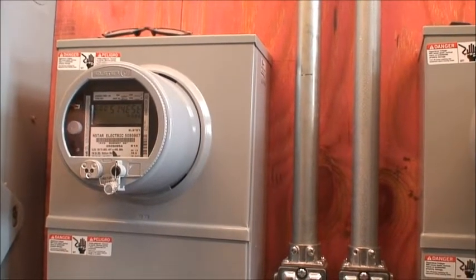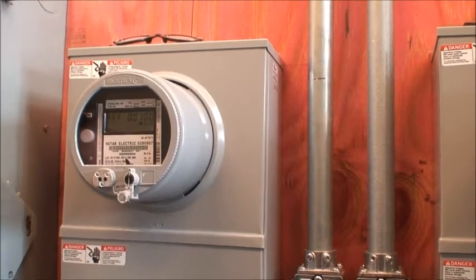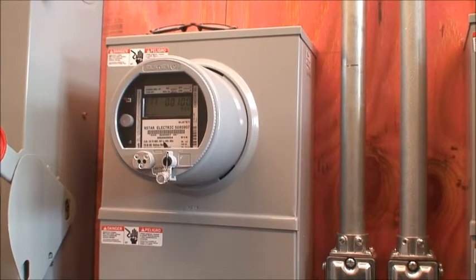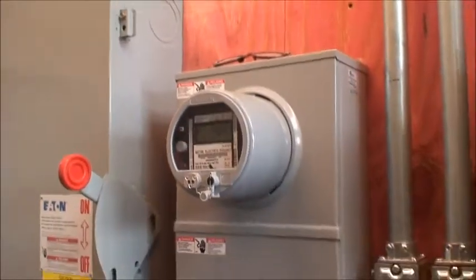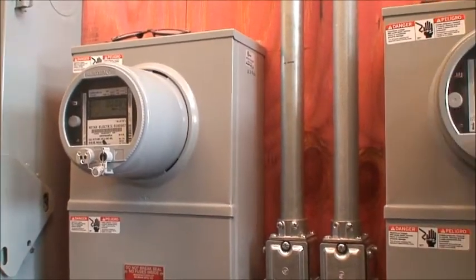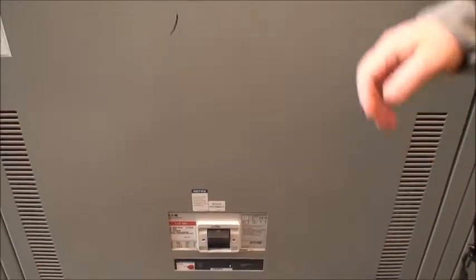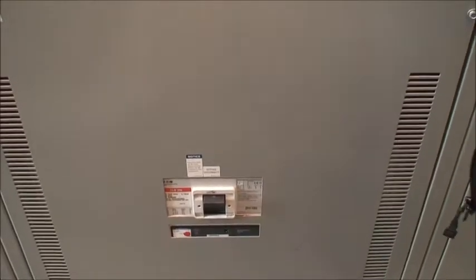And they've got their own shut-offs for the electric in there? They don't shut it off here, because they'd have to shut it off within here. They would open up their lock, and they would shut off here, and then inside they have current transformers. They'd actually pull those out before they would change the meter. If they need to do any service on their end, they can shut down here. This is called cold sequence. So shutting this down shuts off the power to the current transformers. They'd pull their current transformers out, and then they would change the meter if the meter needed to be changed. And then they would put their transformers back in and plug the meter.